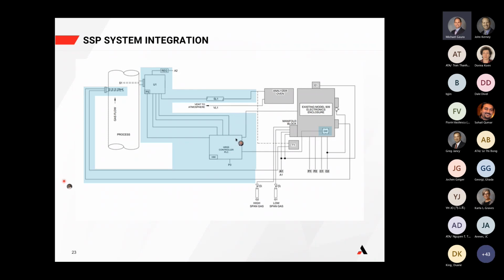That includes the controller. I think I saw a question come up: where does the controller reside in this arrangement? It's going to sit right here, off between the analyzer, which should already exist, whether it's a AMETEK 909 or 910, 919, 920, doesn't really matter. That analyzer would exist, and then the controller would sit between it and the actual blowback probe assembly, which is going to be mounted on the stack here. And again, all the blue highlighted components would typically be provided. We may or may not need to include a gateway depending on how the original analyzer shipped out.